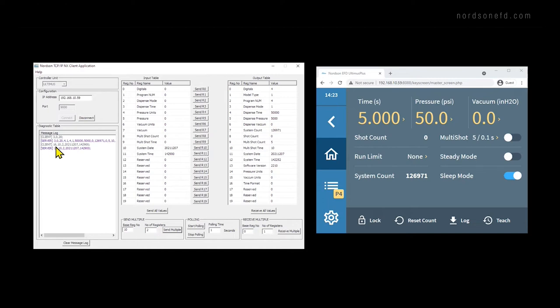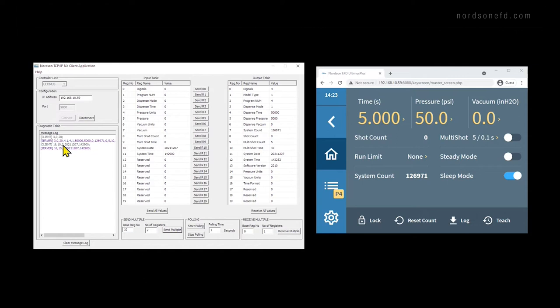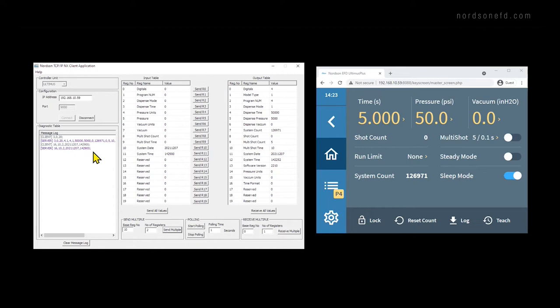You can see in the message log that we sent a new command that starts with a 16. The 16 means that we're sending values rather than receiving them. Then the second number still corresponds with the first register that we want to send or receive, in this case 10. And the third value still represents the number of registers, in this case 2. Then, because we're sending values, what follows are the values that we're sending, separated by commas. And finally, we end the command with a semicolon. Then the server repeats back the command. However, you'll notice that the system time did not change yet.